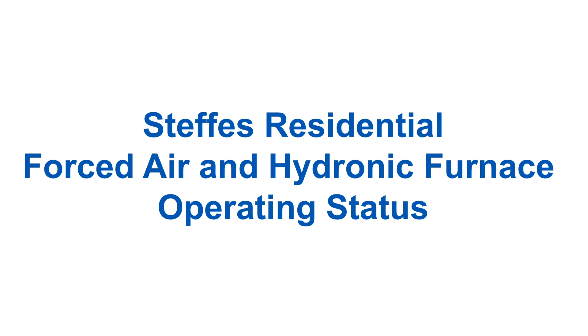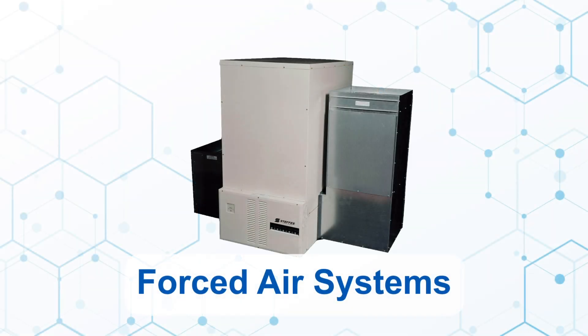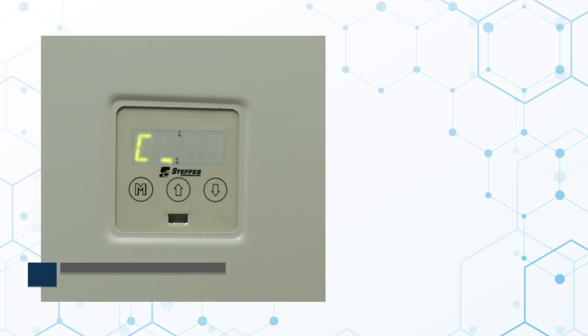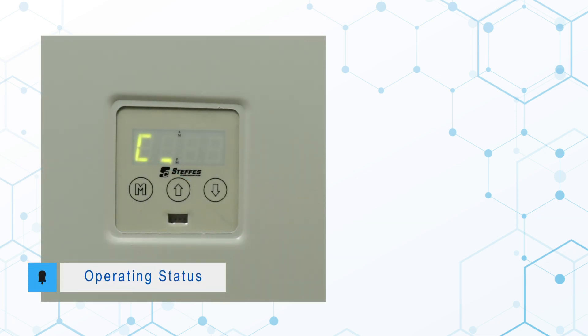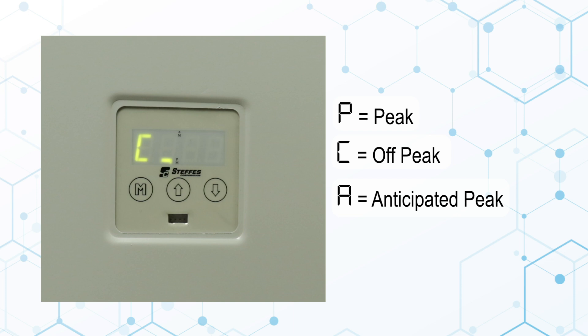Steffes Residential Forced Air and Hydronic Heating Systems are programmed to have various operating information accessible through the display. The normal operating display on a residential forced air system will show the current peak mode status. P indicates the system is in a peak period, C indicates a charge period, and an A indicates an anticipated peak period, if applicable.